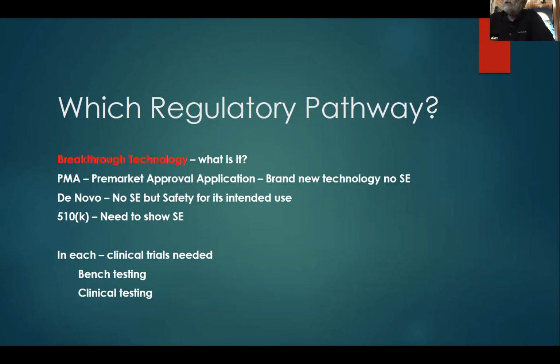The PMA route is the pre-market approval application. It's the most difficult way of getting a product through. It's normally a brand new device or a brand new technology that there is no substantially equivalent for, and the use of it could represent some safety hazards to the patient or to the medical community that's prescribing or using the technology. This normally is the longest pathway, and it's the most expensive pathway in getting a product through the FDA.